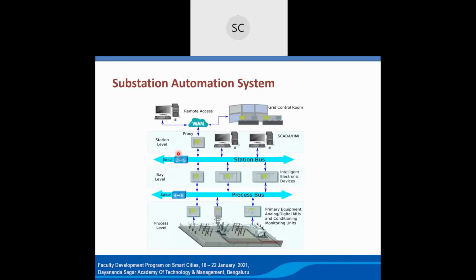So here, how it talks from the station bus, all this IED data goes through the IEC 61850 protocol. Right now, at present, IEC 61850 cannot directly talk to the distribution automation control center, because in the control center we are using a different communication protocol that is built on IEC 60870-5-101 or 104. Nowadays we are using the 104 protocol, which is built on Ethernet or TCP/IP. So the 61850 protocol cannot directly talk to this 104 protocol. So we will have gateways at the station bus level, where all the data through the gateway gets converted into 104 and talks to the control centers.